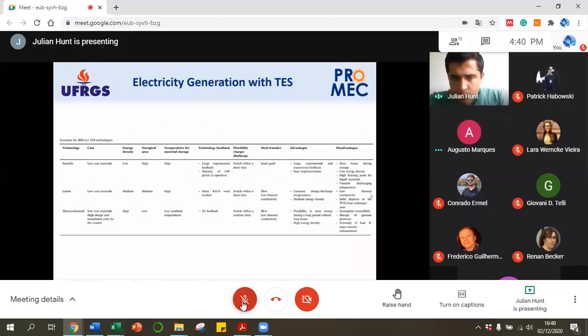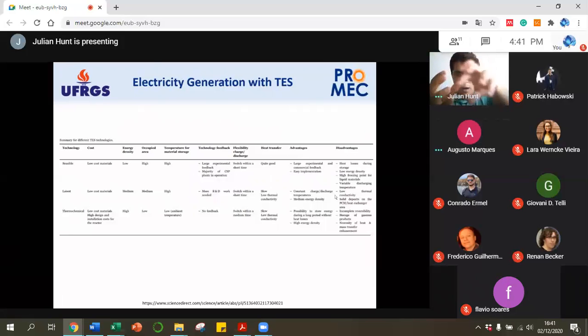The disadvantage is low thermal conductivity. As I mentioned, with latent heat, the main issue is low thermal conductivity, mainly when the material solidifies, for example salts have very low thermal conductivity when solid. So when you melt, you only melt a small part, and the heat doesn't melt the whole tank. And when you want to fuse the salts, the solid forms around the heat exchanger, so you won't have heat exchange between the hot fluids inside and your storage tank, which is the main issue with latent heat thermal energy storage.